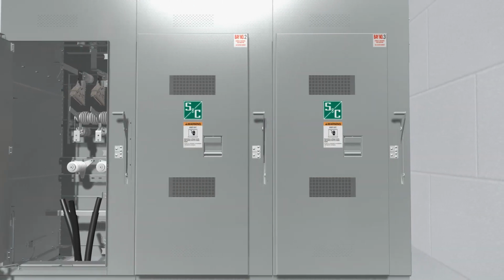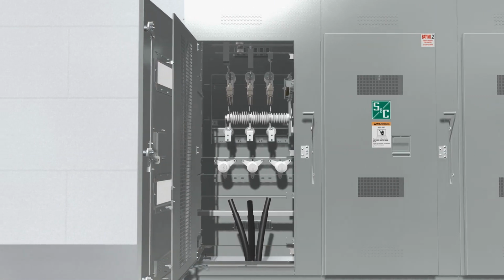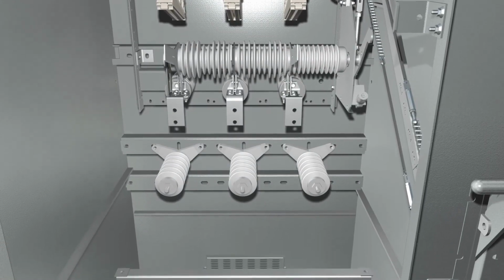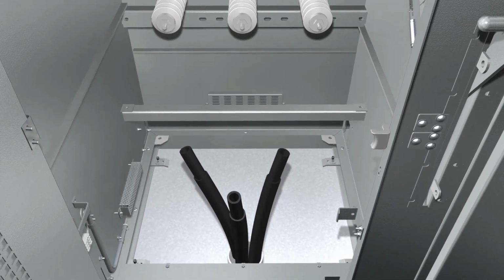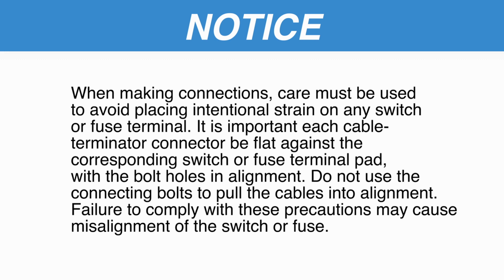Following the user's established system operating safety procedures, check to make certain connection of the incoming power sources to the switchgear terminals is in the proper phase sequence. Note: When making connections, care must be used to avoid placing intentional strain on any switch or fuse terminal. It is important that each cable terminator connector be flat against the corresponding switch or fuse terminal pad with the bolt holes in alignment. Do not use the connecting bolts to pull the cables into alignment. Failure to comply with these precautions may cause misalignment of the switch or fuse.